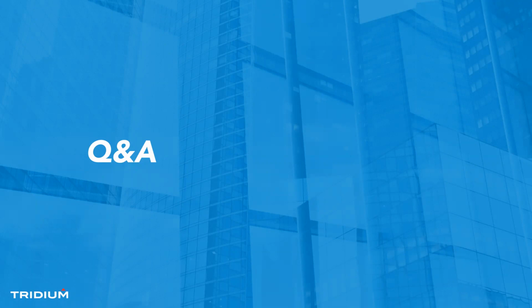Okay, and if I have any custom or unique modules installed on some of the JACEs down at the edge, do I also need those installed on the supervisor in order for this to work? I think it would be a good idea. The virtuals may resolve even if you don't have them installed. I'd have to double check, but typically supervisors are going to have all of the modules because they have plenty of resources. So there's no reason not to have the modules up at the supervisor that you have on the downstream JACEs and edge controllers. I think most often you will have those jars already up there.